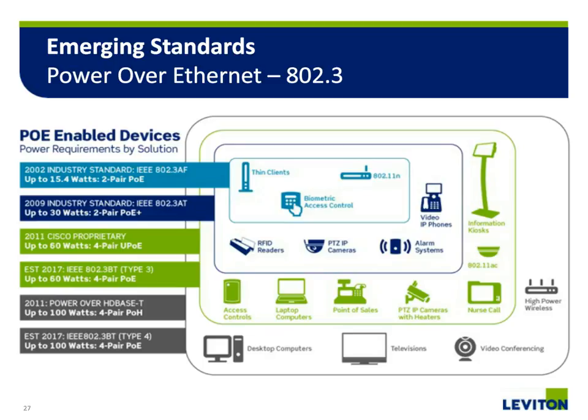This is a pretty significant step, two reasons. Number one, the standard very clearly limits the power to 100 watts or less. And the reason for that is because NEC code talks about the fact that if you're going to have a low voltage system, it can't exceed 100 watts. So we want to make sure that PoE standards don't require different licensing and different types of certifications to install it. And then the second thing is 100 watts is a lot of power. Imagine the ability to power a television over your Ethernet cable. That's a pretty significant advantage. And one of the things that you'll notice is if you can power a laptop over the Ethernet cable, all of a sudden people are going to want to have Ethernet connections all over the place and not simply just the wireless connection. So these are some exciting things that are going to allow copper cabling systems to stick around for a long time.